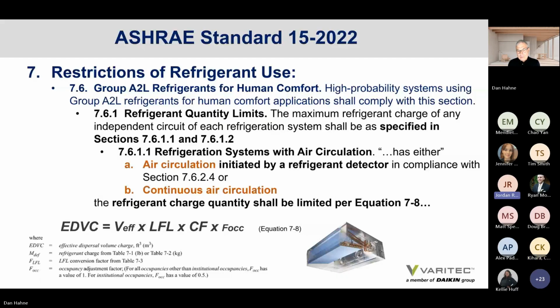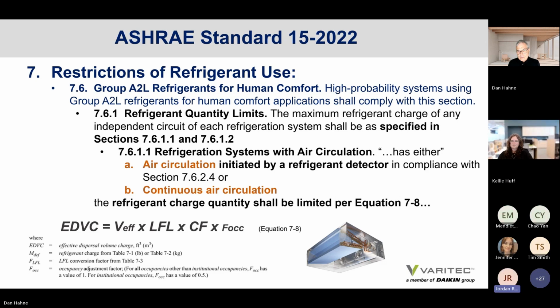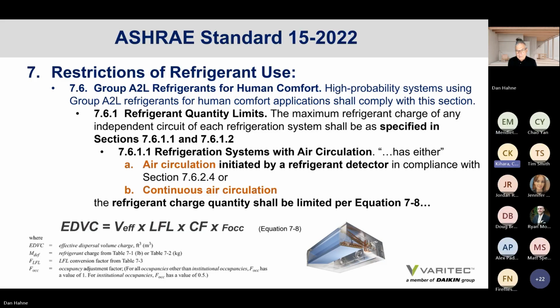Well, and that's exactly my question, Kelly: is it interchangeable, or are they two specific separate metrics and both calculations have to occur, one for toxicity control limit, RCL, and one for the LFL limit for flammability? They're two separate things, because one takes into account flammability. The other one, because in an A1, it's not flammable. A2Ls were created separately. It's a separate category because they were slightly flammable, so they're not full on A2s. That's why the L is there, for the lower, slightly flammable aspect of it.